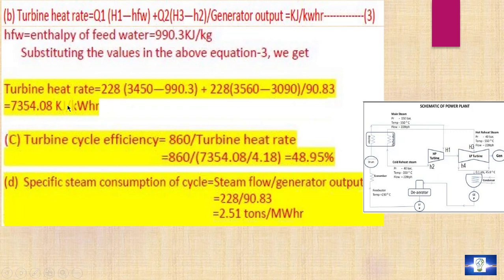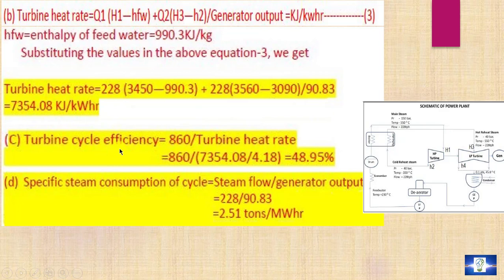The third question is turbine cycle efficiency. The turbine cycle efficiency equals 860 divided by the turbine heat rate in kcal/kWh. So: 860 / (7354.08 / 4.18), converting kJ to kcal. The turbine cycle efficiency is 48.95%.